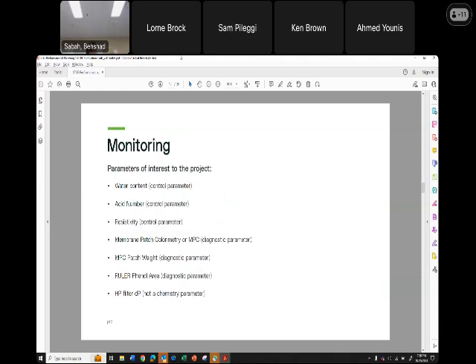Okay, so as I mentioned, at Pickering, we started a project to apply the EPT technology to the Pickering units. We're applying the TMR N2 gas purge on top of the headspace of the tank to remove water. We're using electrostatic filtration to remove the insoluble varnish and any particulate. And we're using IX resin to pull out varnish, acid, phenols, and that sort of thing.